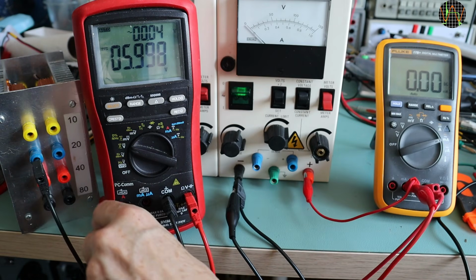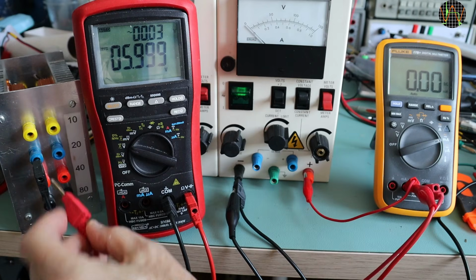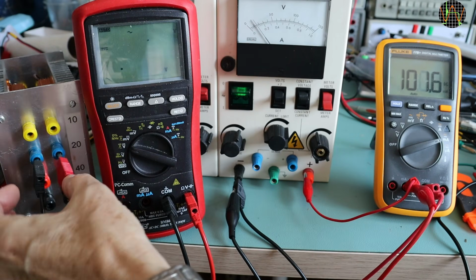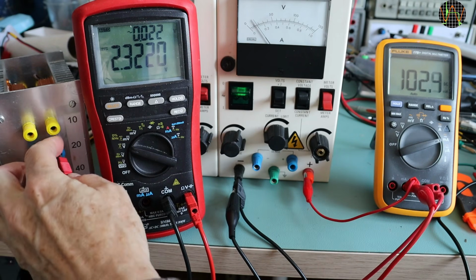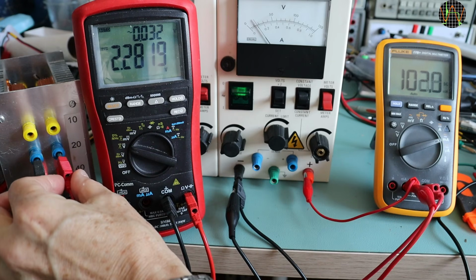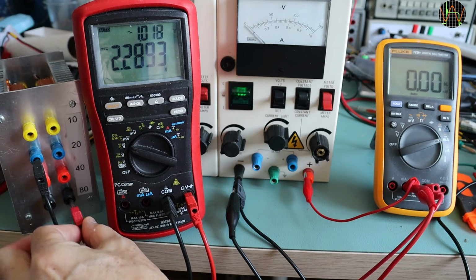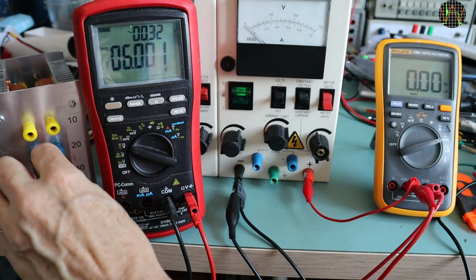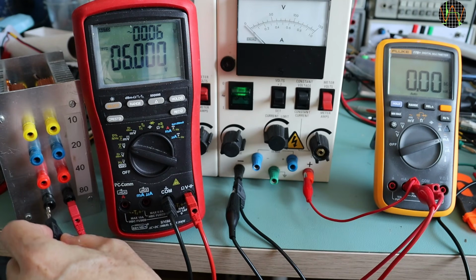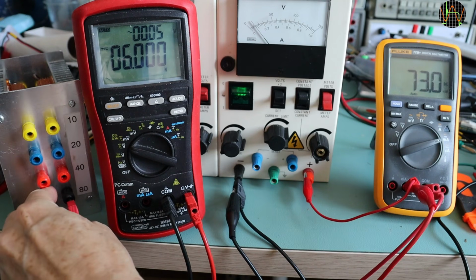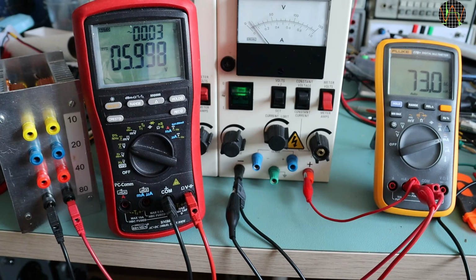I can now connect the device, in this case a 20 ohm resistor, and as expected the voltage collapses because the current limit is exceeded. But if the device is, say, repaired and now draws much less, simulated by the 80 ohm resistor, the 6 volts is maintained because 73 milliamps of current is below the limit. Under all circumstances, the voltage never exceeded 6 volts, the safe operating voltage set at the beginning.